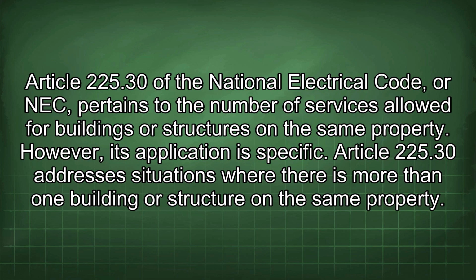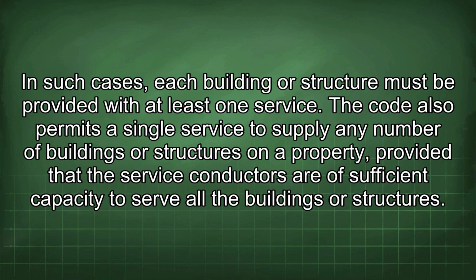Article 225.30 addresses situations where there is more than one building or structure on the same property. In such cases, each building or structure must be provided with at least one service. The Code also permits a single service to supply any number of buildings or structures on a property, provided that the service conductors are of sufficient capacity to serve all the buildings or structures.